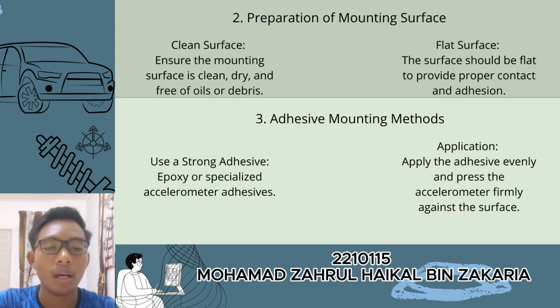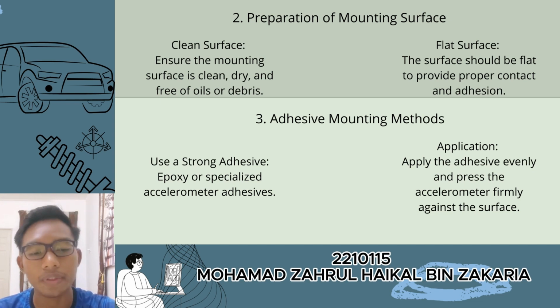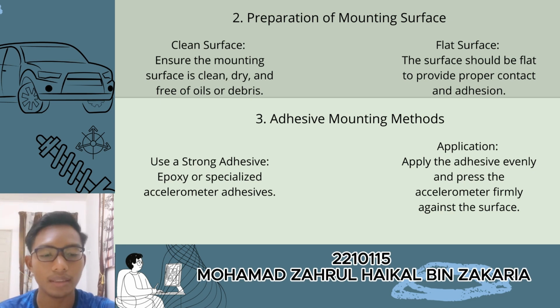Secondly, we must prepare the mounting surface. Ensure the mounting surface is clean, dry and free of oils or debris. The surface should be flat to provide proper contact and adhesion. Thirdly, we use adhesive mounting. Use a strong adhesive, for example, epoxy or a specialized accelerometer adhesive. Apply the adhesive evenly and press the accelerometer firmly against the surface. Allow curing as per the adhesive instructions.